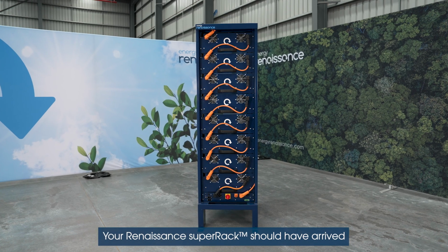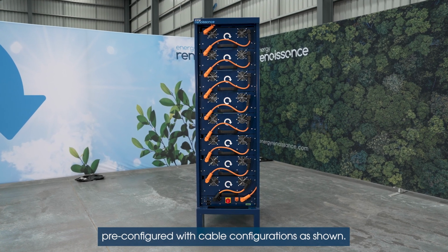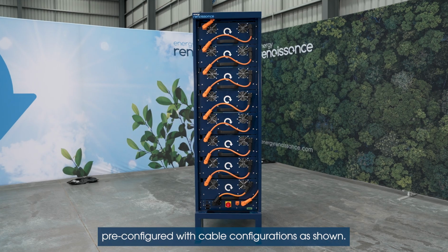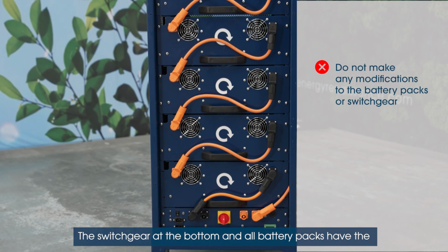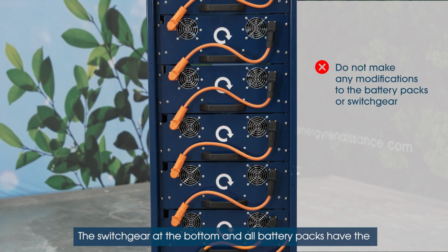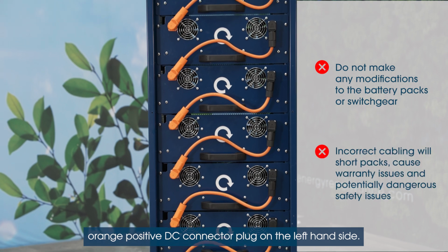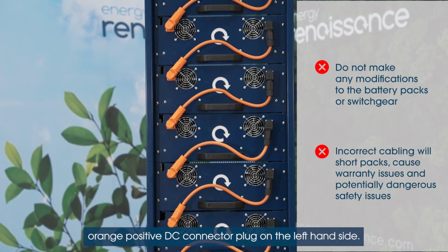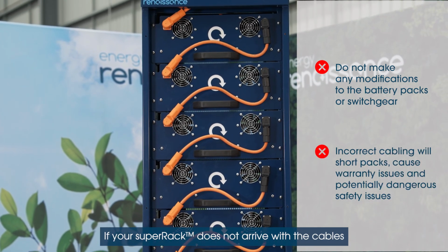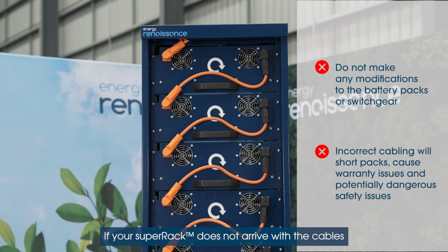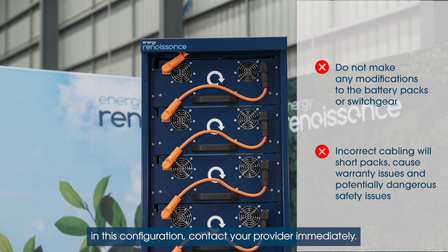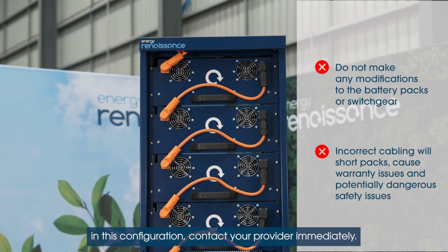Your Renaissance superRack should have arrived pre-configured with cable configurations as shown. The switchgear at the bottom and all battery packs have the orange positive DC connector plug on the left-hand side. If your superRack does not arrive with the cables in this configuration, contact your provider immediately.